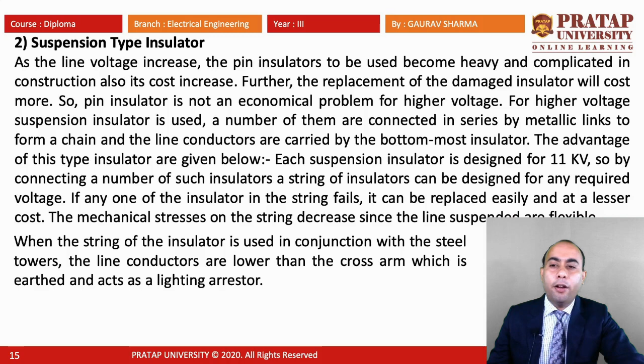So, we are using the suspension type insulator. For higher voltages, the suspension insulator is used. A number of them are connected in series by metallic links to form a chain, and the line conductors are carried by the bottommost insulator. The advantage of this insulator is that each unit is designed for 11 kV. So by connecting a number of such insulators, a string of insulators can be designed for any required voltage.